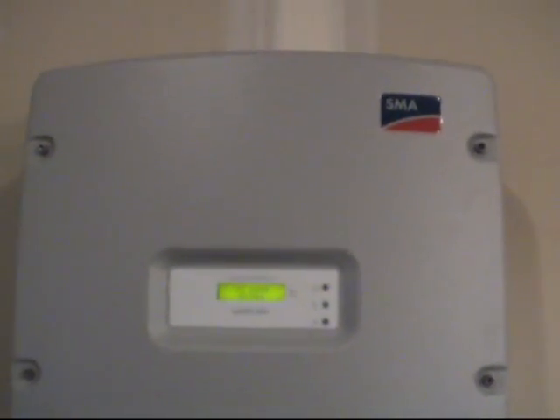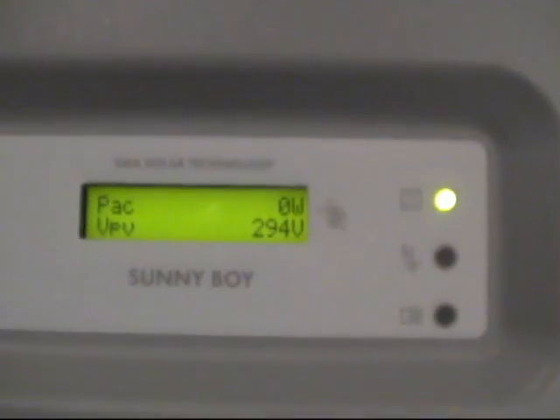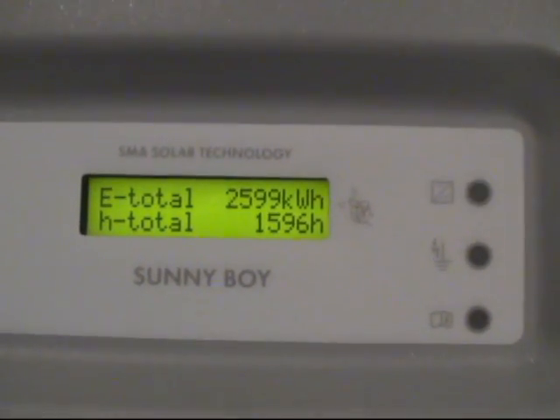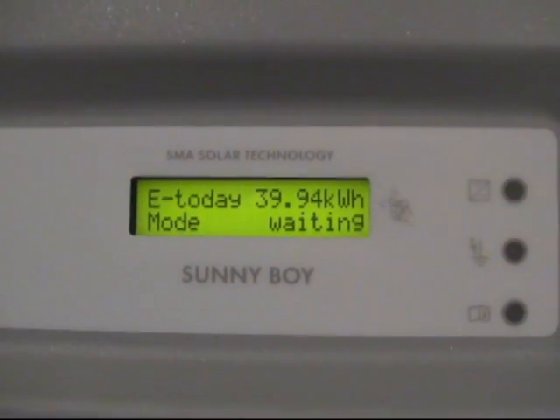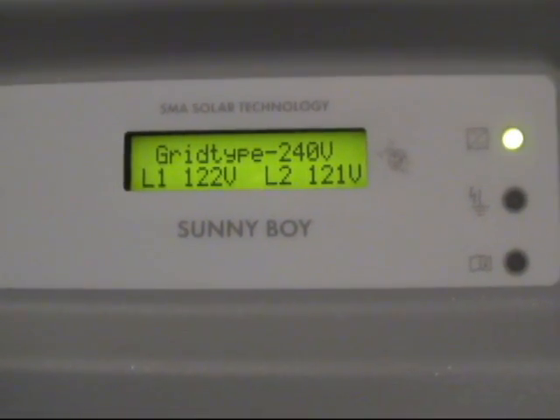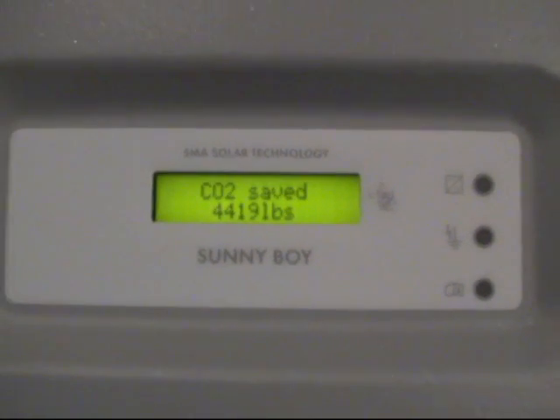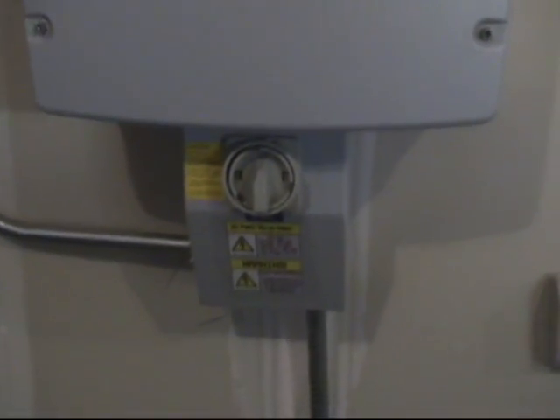The conduit comes down the garage wall and feeds into this DC disconnect and goes up into this SunnyBoy 7 kilowatt inverter. The inverter is off right now — it's flashing and going through some of its status. It made just shy of 40 kilowatt-hours today, not a bad day for end of April. This inverter does a fantastic job of efficiently converting the 500 volt DC down to 240 volts AC, which then feeds down through this other conduit through this cutoff box into my basement.